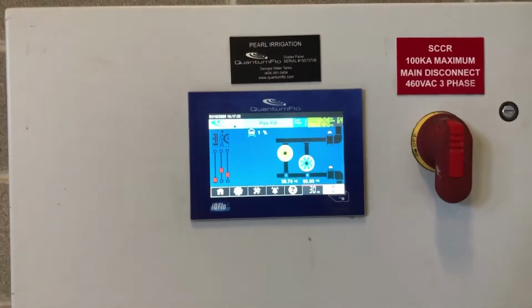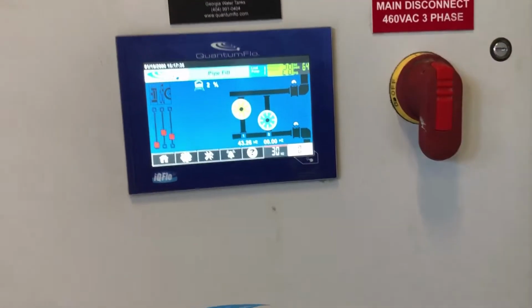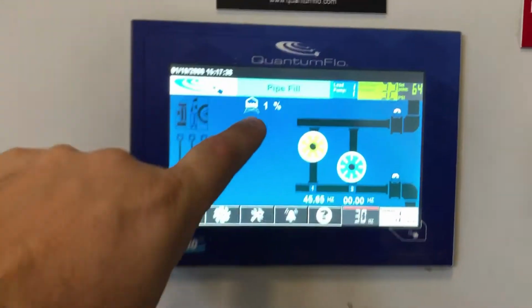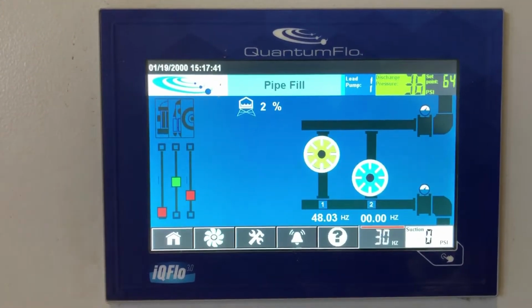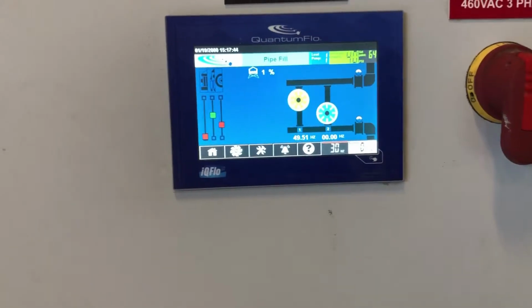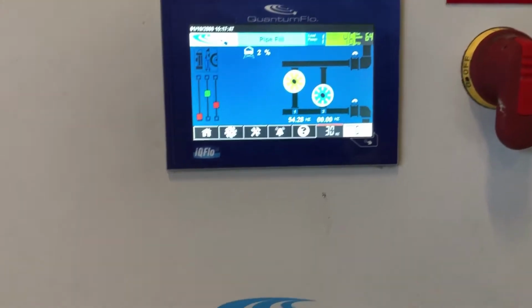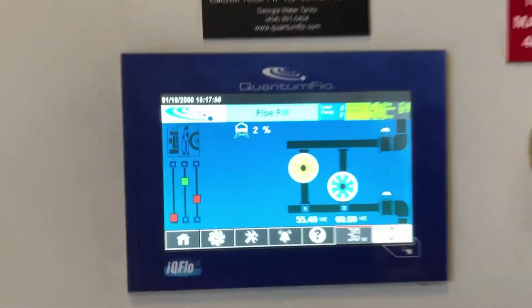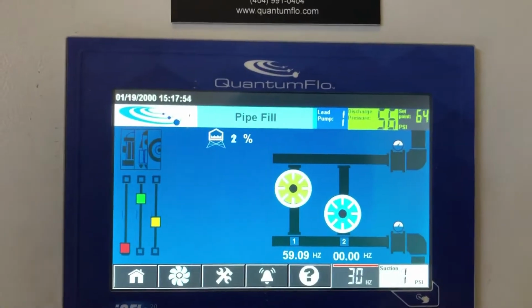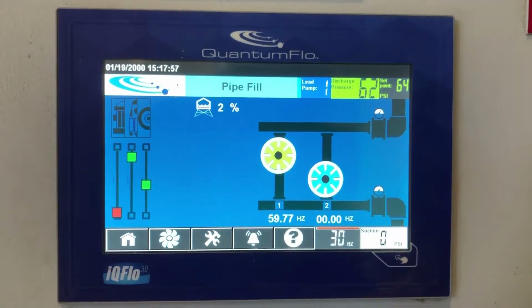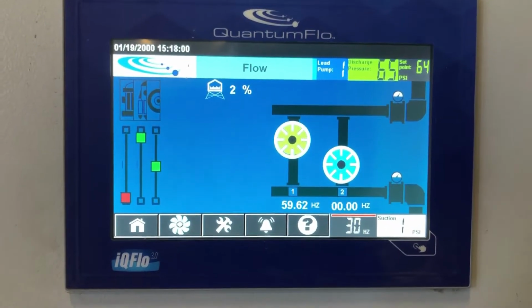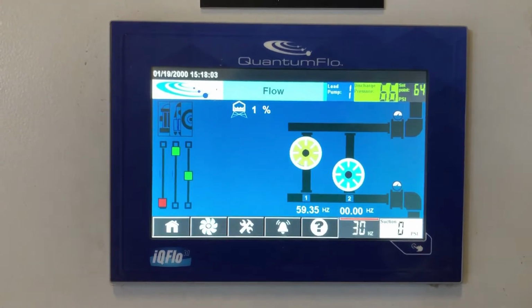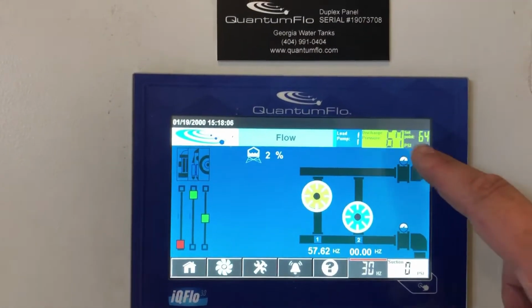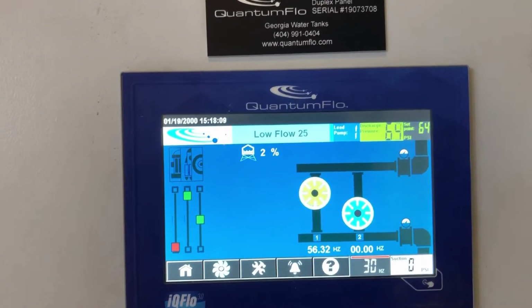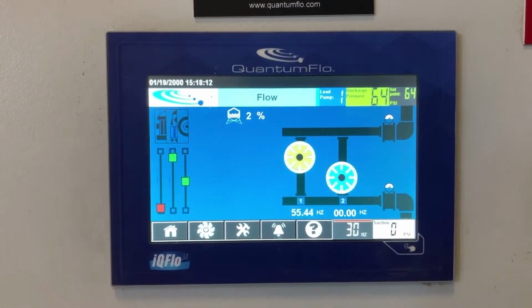Here's the control panel for it. Just turned it on so it's starting up. We have 2 submersible pumps, as you saw in the drawing earlier. We're showing 1 or 2% of tank filled, which looks about right. Started 1 pump. That's the green there. These pumps only need about 3 inches of cover in order to work. They're really great for fully utilizing these tanks. So you see the pump has gone up to 66 psi. Over the set point, it's starting its low flow shutdown.